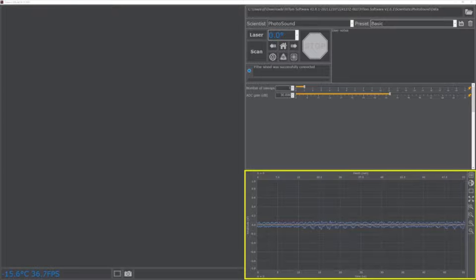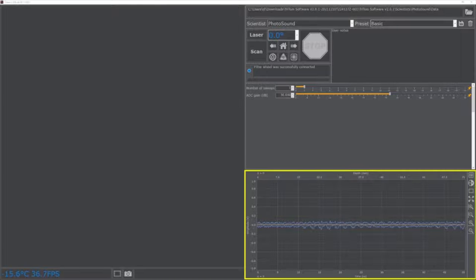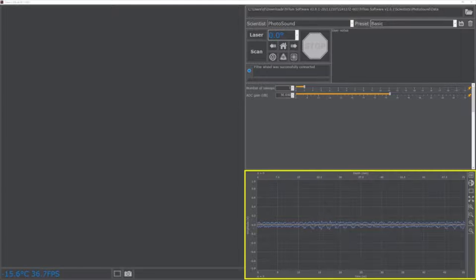The blue plotline displays the maximum and minimum values of all channels across all ADCs. If the photoacoustic signal surpasses the ADC limit, the blue channel turns red to notify the user that the acquired signal is saturated.